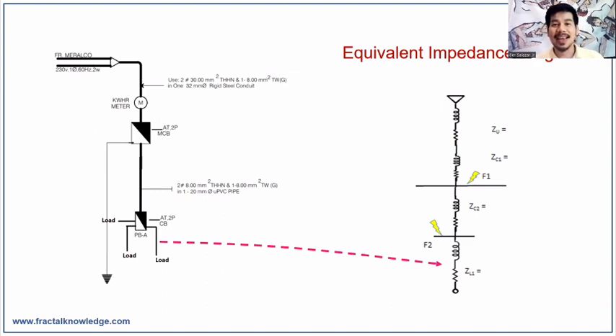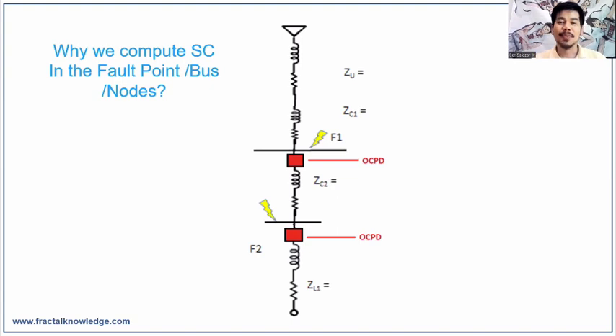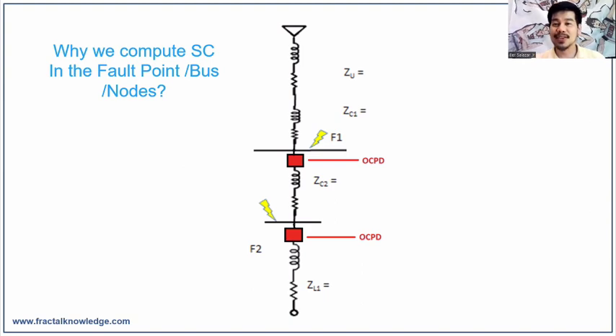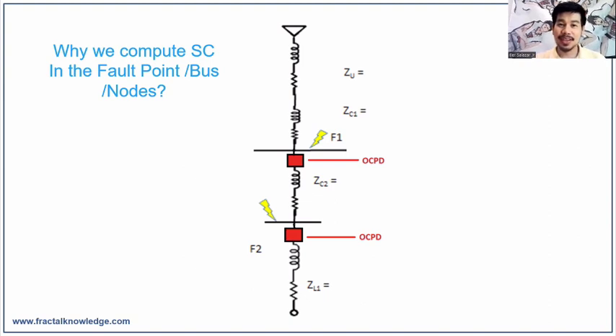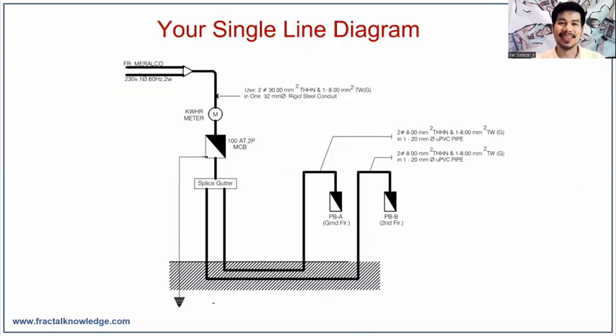Bus 2 represents the load panel with the main breaker, where we will compute fault number 2. Finally, here is the lamp load. This is the complete impedance diagram shown step by step. You may ask why we need to compute the short circuit at Bus 1 and Bus 2 — because we specify the size of the overcurrent protective device but do not yet know the kAIC rating of those circuit breakers. Once we compute the short circuit there, we can specify the kAIC rating.